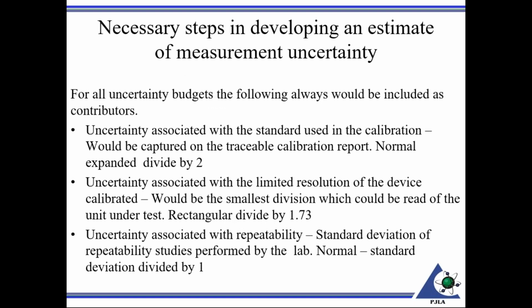So, uncertainty budgets. The way I like to present it for calibration is that there are typically always 3 contributors that would be looked at. Beyond that, it pretty much depends on the type of calibration and the other sources that would be added to these 3. First, you always have an uncertainty associated with the standard used in calibration. That would typically come off the calibration report, and it would be divided by the k factor off the calibration report.